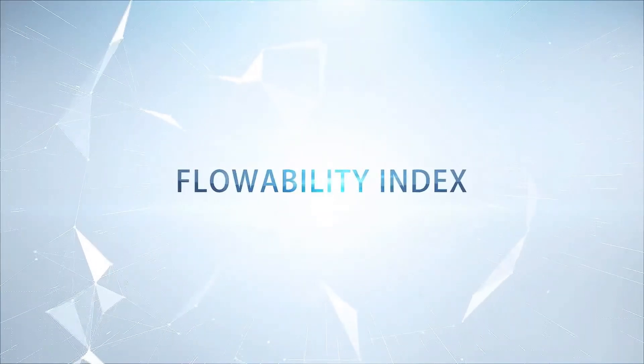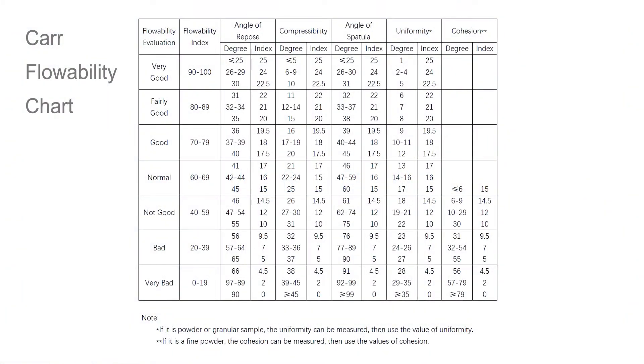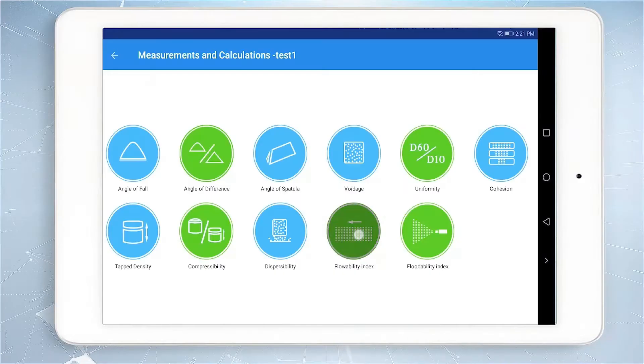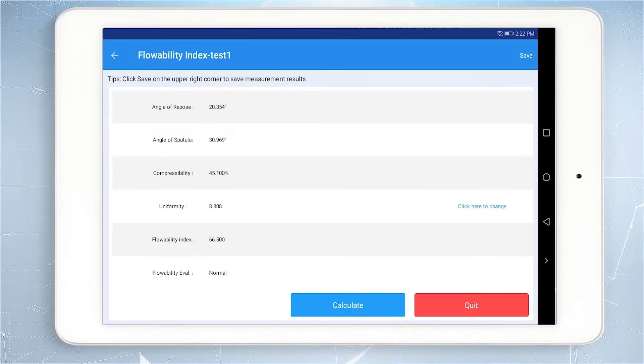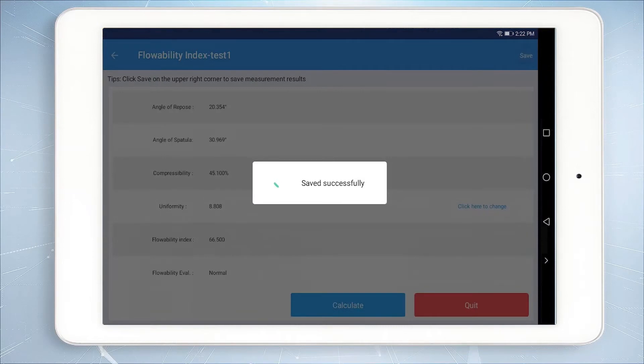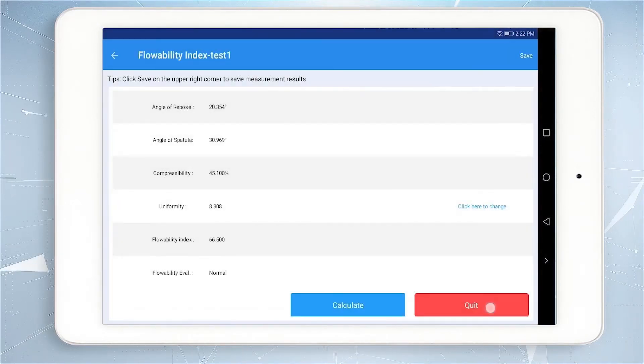The flowability index is the weighted sum of the angle of repose, compressibility, the angle of spatula, and uniformity or cohesion. After these values are measured, click Flowability and click Calculate to get the flowability index and flowability evaluation. Then click Save and Quit to complete the flowability evaluation.